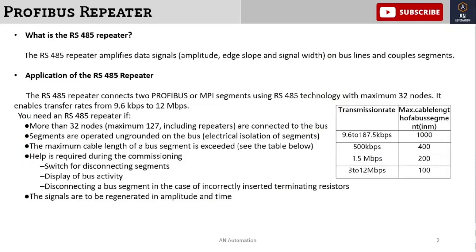What is an RS485 repeater? The RS485 repeater amplifies the data signal — that is, it amplifies the local signal across all bus lines and couples segments. The RS485 repeater connects two Profibus or MPI segments using RS485 technology with a maximum of 32 nodes, enabling transfer rates from 9.6 kbps to 12 Mbps.